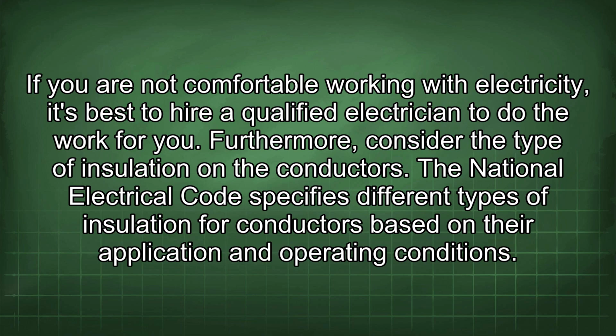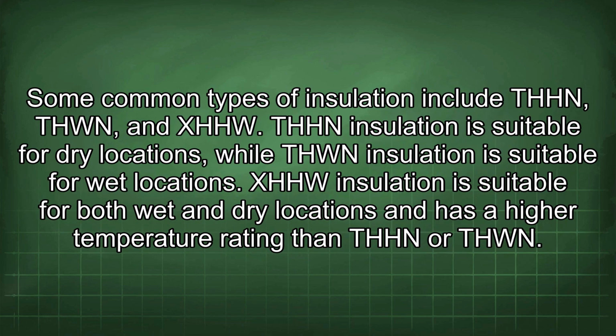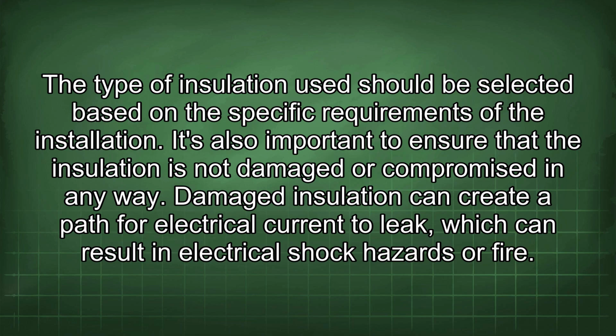The National Electrical Code specifies different types of insulation for conductors based on their application and operating conditions. Some common types of insulation include THHN, THWN, and XHHW. THHN insulation is suitable for dry locations, while THWN insulation is suitable for wet locations. XHHW insulation is suitable for both wet and dry locations and has a higher temperature rating than THHN or THWN. The type of insulation used should be selected based on the specific requirements of the installation.